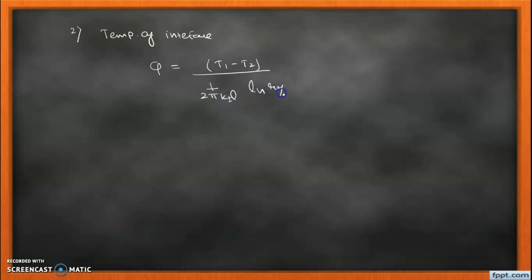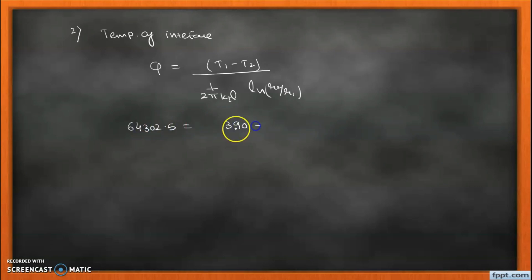Now we calculate the interface temperature T2. Applying the heat flow equation for the first layer only: Q = (T1 − T2) / R1 = (T1 − T2) / [(1 / 2πk1L) · ln(r2/r1)]. We know Q = 64,302.5 W, T1 = 390°C, k1 = 0.092, L = 210, r2 = 170, r1 = 120.